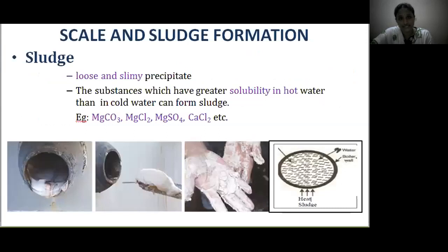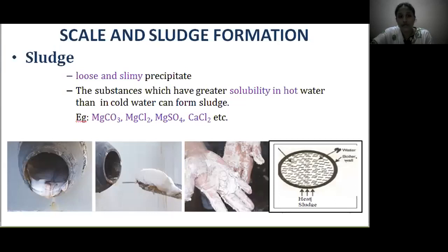What are sludges? They are loose and slimy precipitates formed in the boiler. Substances like magnesium carbonate, magnesium chloride, magnesium sulphate, and calcium chloride have greater solubility in hot water than in cold water. Sludges are usually formed at the colder portions of the boiler.